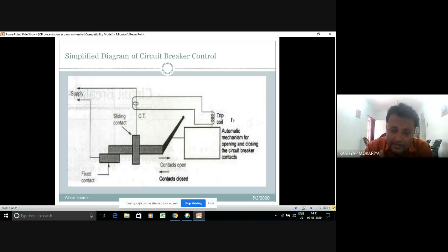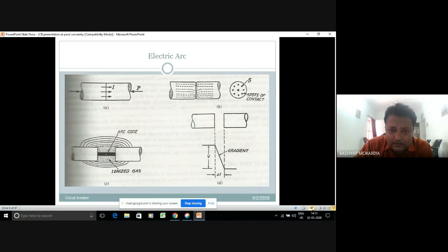So one breaker is looking after a different amount of voltage for a motor, or if we compare it to feeder action, then also it will give tripping against the fault. So these are some very basic things about the circuit breaker. Now, if I keep it very simple, there are two types of arc extinguishing principles: a high resistance interruption and a low resistance interruption. Take an example of a DC circuit breaker.